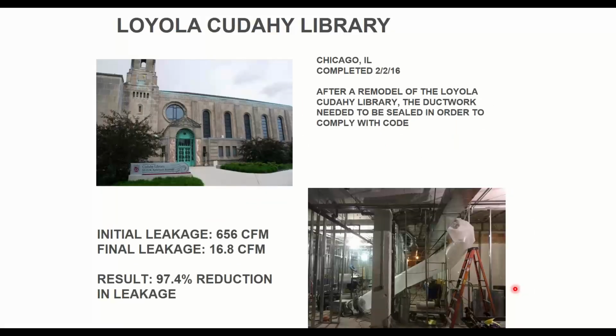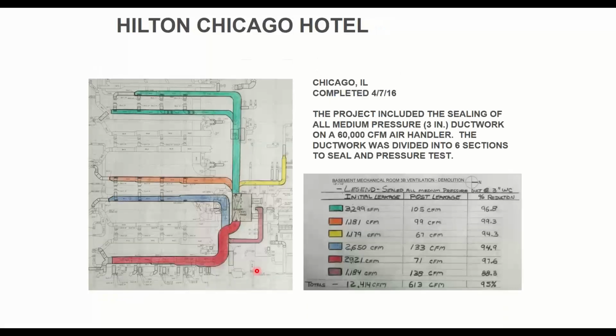Here's a university library, similar small project, early job. This was just for some specific spaces in the library, so it was a fairly small system. But still, they had 600 CFM in leakage, got it down to 17, which is really, really low. It's basically almost immeasurable. This job, this is my favorite. This is now 6 years ago that one of the guys did this job.